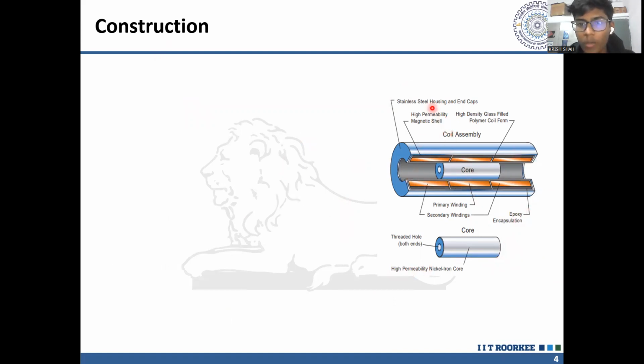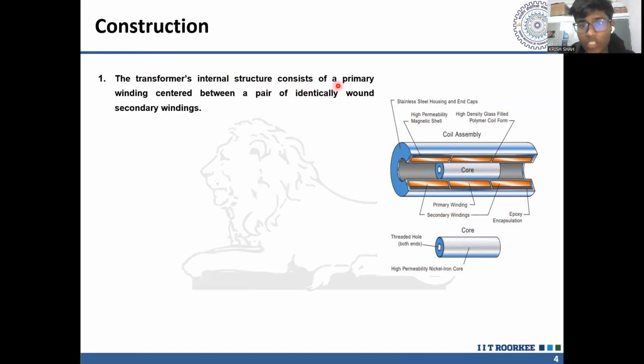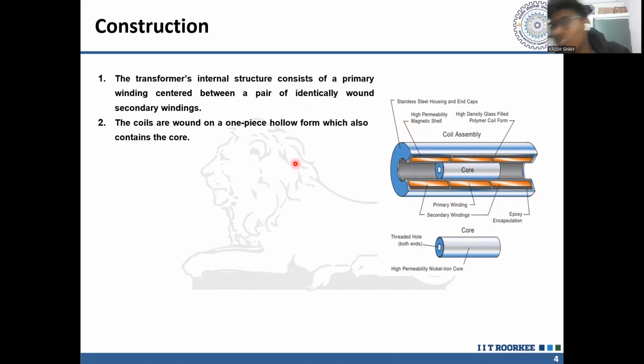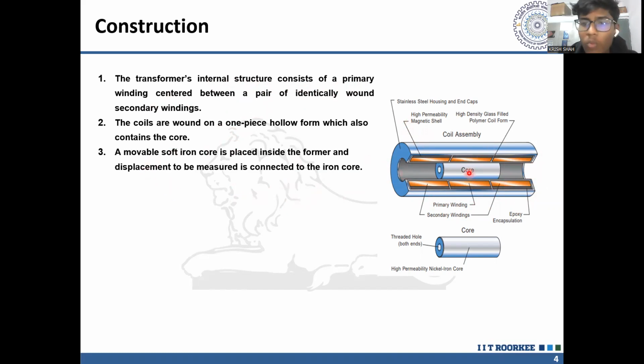The LVDT consists of a primary coil, a core, a form, and two secondary coils outside the primary winding. The transformer's internal structure consists of a primary winding, here this golden thing in the center, and a pair of identical secondary windings on the right and left sides of the primary winding. All this is placed inside a hollow form, which ensures that outside inductive interference is not allowed. A movable soft iron core is placed inside this hollow form, with a little difference between the outer radius of the core and the inner radius of the hollow form to ensure smooth movement of the core.